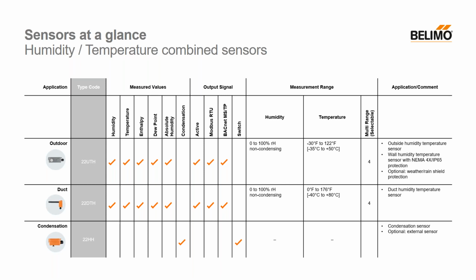The condensation switch is really just that. It's a basic condensation switch that is powered. So one thing you have to keep in mind is that it's not a dry contact that's associated with our condensation switch. It has to be a powered application. So you'll have to send 24 volts to that condensation switch for it to be active and closed.